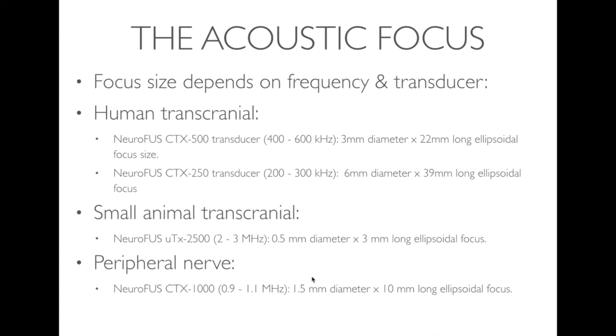With NeuroFUS, we've got a range of transducers available that enable you to stimulate from 200 to 600 kilohertz. One transducer operates between 400 and 600 kilohertz, and the size of the focus is absolutely tiny - about 3 millimeters in diameter and 22 millimeters in length. Think of it as the shape of a cigar or a grain of rice, an ellipsoid. We've also got one that operates at a slightly lower frequency of 250 kilohertz, which gives a slightly larger focus of 6 millimeters by 39 millimeters in an ellipsoid shape.